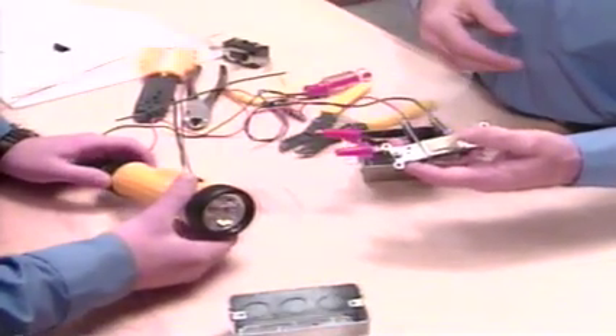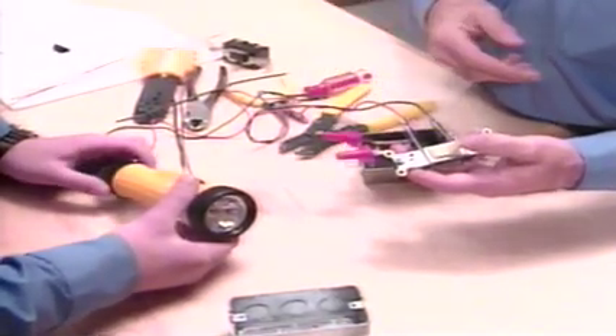Well, how do you know that? Because when the switch is off, what happens to the path of electricity? It's broken because the switch is open? Exactly. And when the switch is on? The switch is in a closed position, so the path of electricity is not interrupted. Right. We have continuity. All right. Now, what would you conclude if the switch was on and the continuity tester light didn't come on? That would mean that the switch was bad or it was wired wrong. You catch on quick.